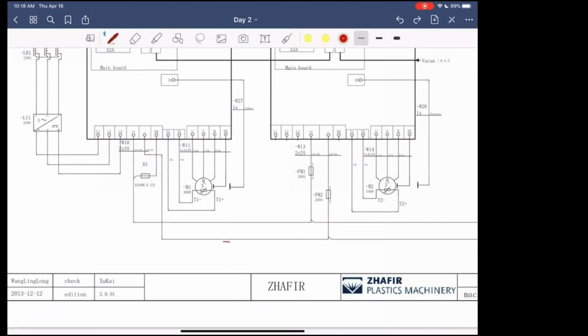The other thing here is you have a T1 and T2. T1 and T2 is a thermistor, which is located on the motor itself, and that keeps track of the temperature of the motor so we don't overheat the motors. And then your line 1, line 2, line 3, or RST, becomes UVW. And you also have an encoder. Your encoder goes to the motor, which keeps track of the position of the motor at all times.